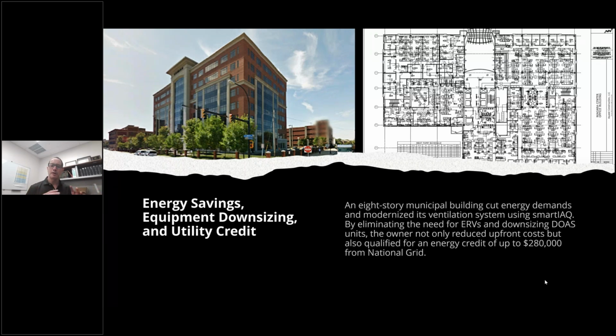What we figured out is, look, you don't need all that extra outdoor air, and we can lower the outdoor air in a way that actually provides significant savings on the DOAS unit itself. That DOAS unit went from roughly a $1.2 million, $1.1 million unit down to about a $600,000 unit. Significant savings there, but even more to the point, the energy we were going to save - the utility company said we can easily write probably more, but for today's conversation, the energy credit was upwards of $280,000, which was going to fund a lot of this project. We're solving this by basically cleaning the air with multiple units on each of these floors.